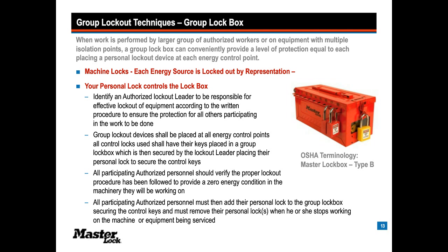A group lockbox should only have the locks of the participants on it during the time frame they are exposed to the hazard. So when I begin working on the task, my lock is the first thing that's placed. I go to work. I get my job done.